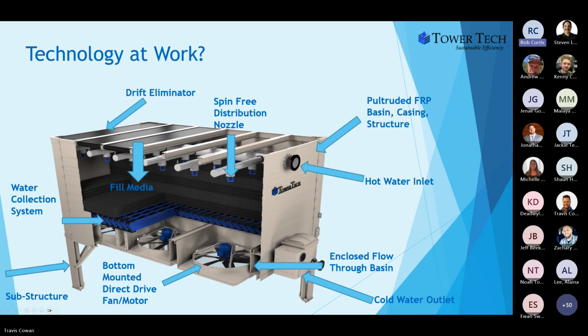So traditionally you have top mounted fans, gearboxes, belts, drive shafts, things of that nature. TowerTech uses a bottom mounted design, which now has the equipment more easily accessible to you, not having to put people up on top of the cooling tower, elevated, in situations where people could slip and fall, especially in icing conditions and things like that. So you can be at grade level, you've got access to your mechanical equipment.